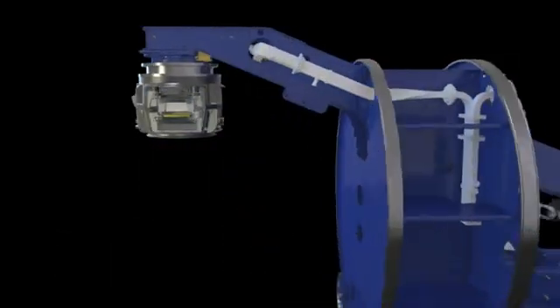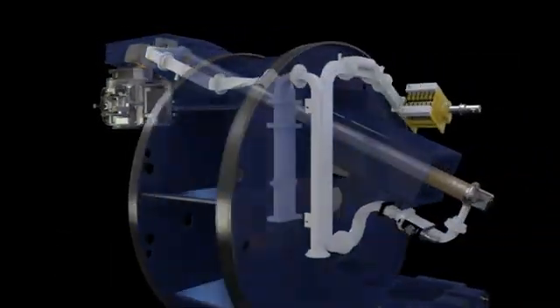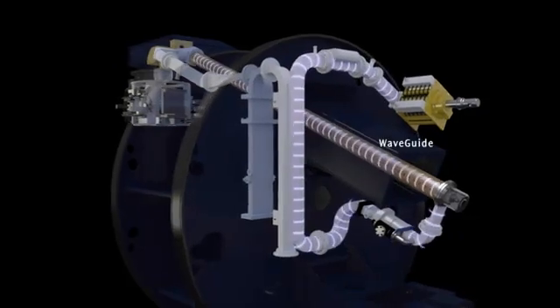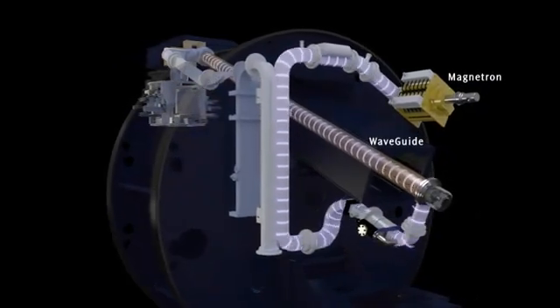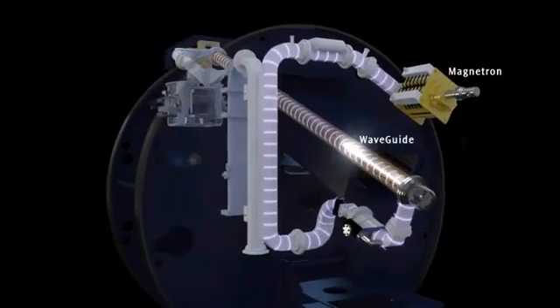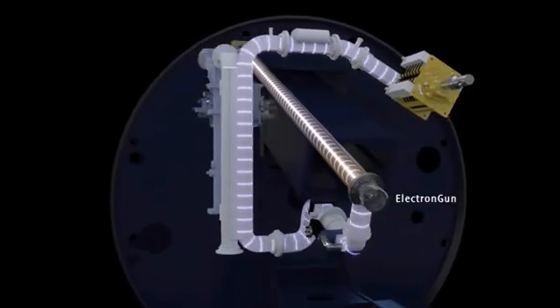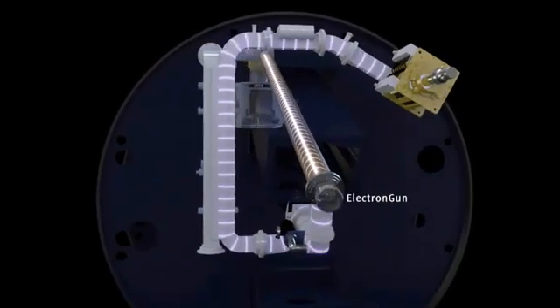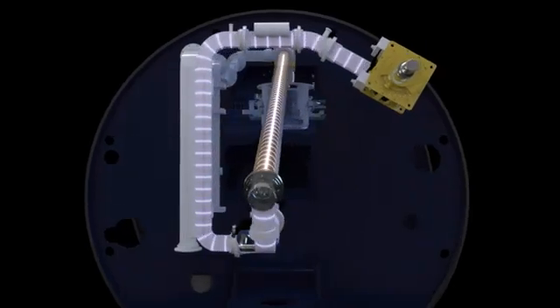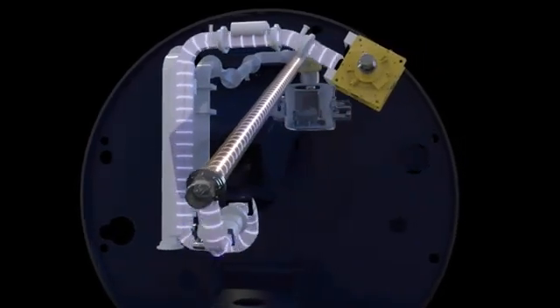Beam Generation. Radio frequency waves are pulsed into the waveguide by the magnetron. This is synchronized with the injection of electrons into the waveguide by the electron gun. The radio frequency waves accelerate the electrons along the waveguide to a speed approaching the speed of light.